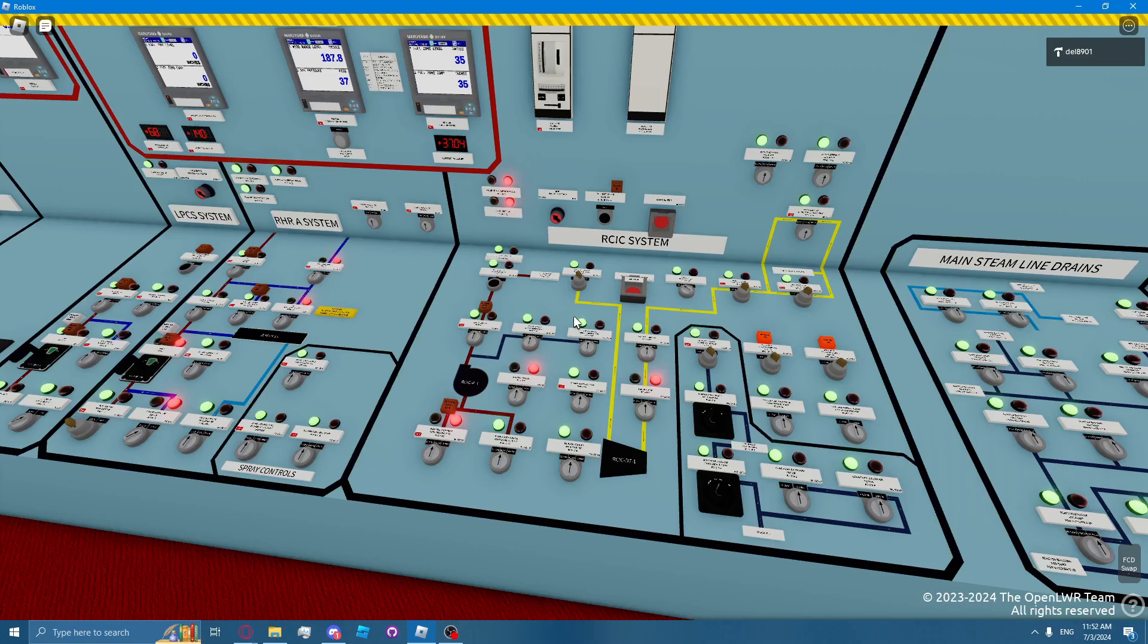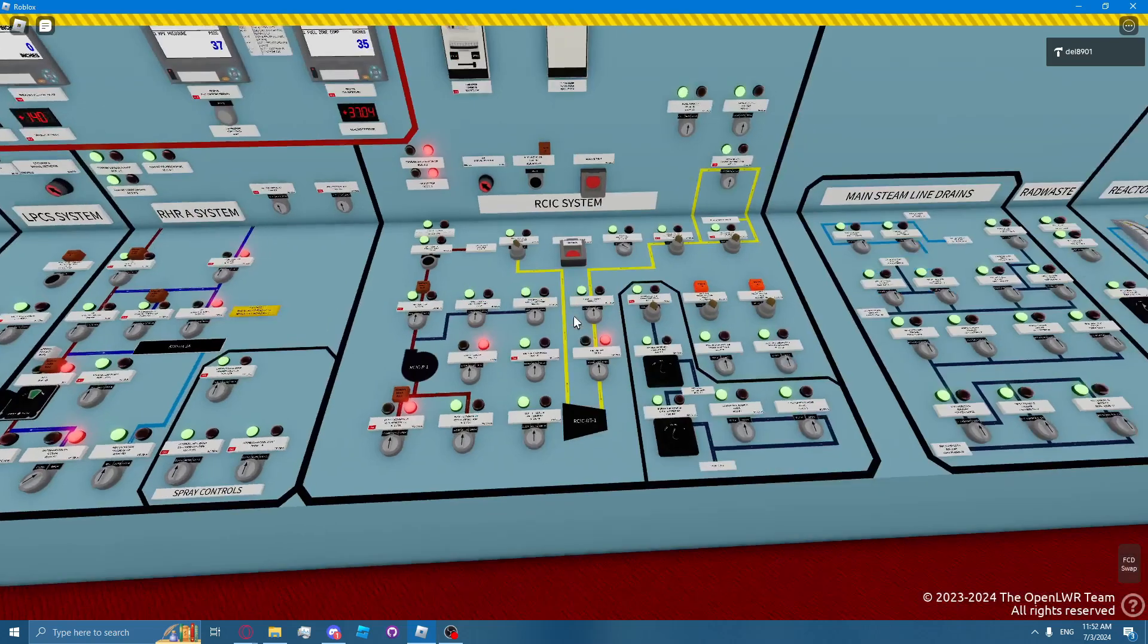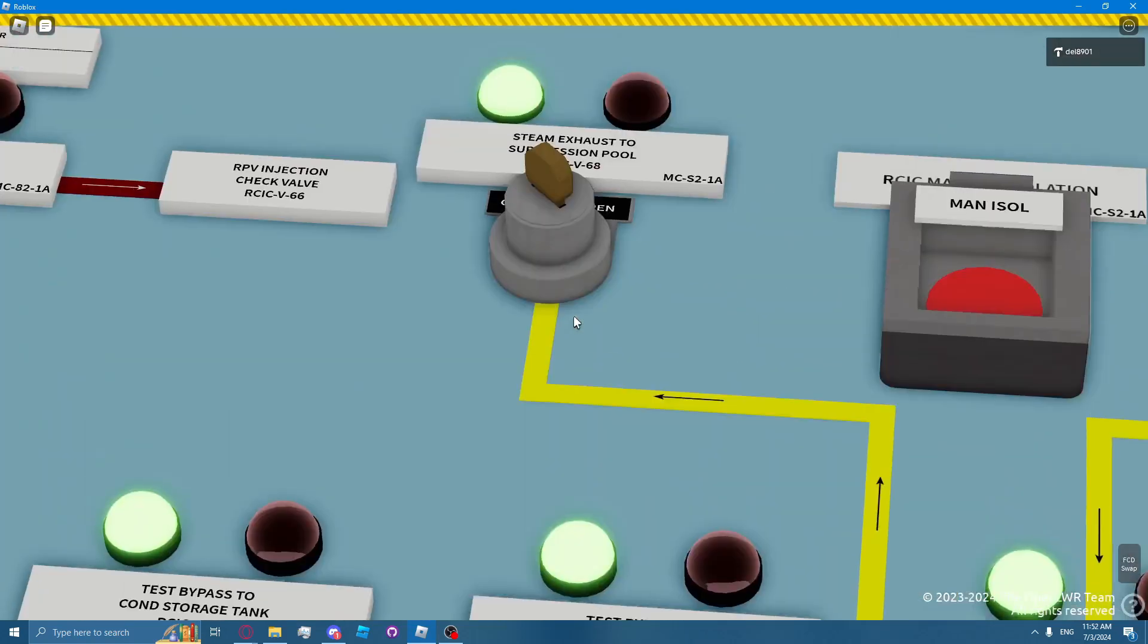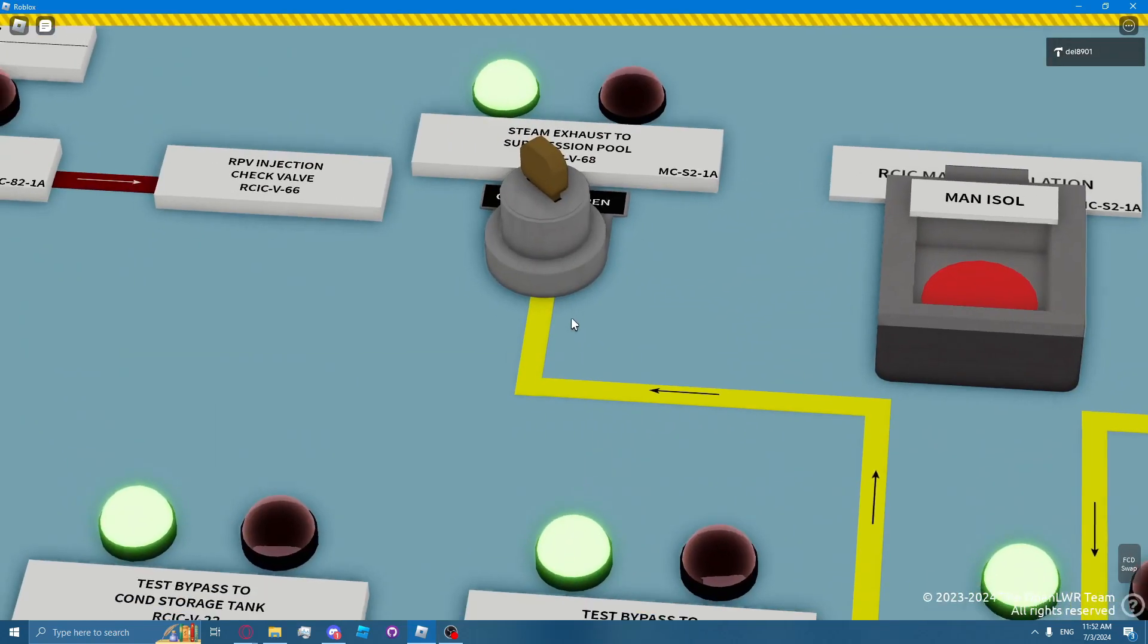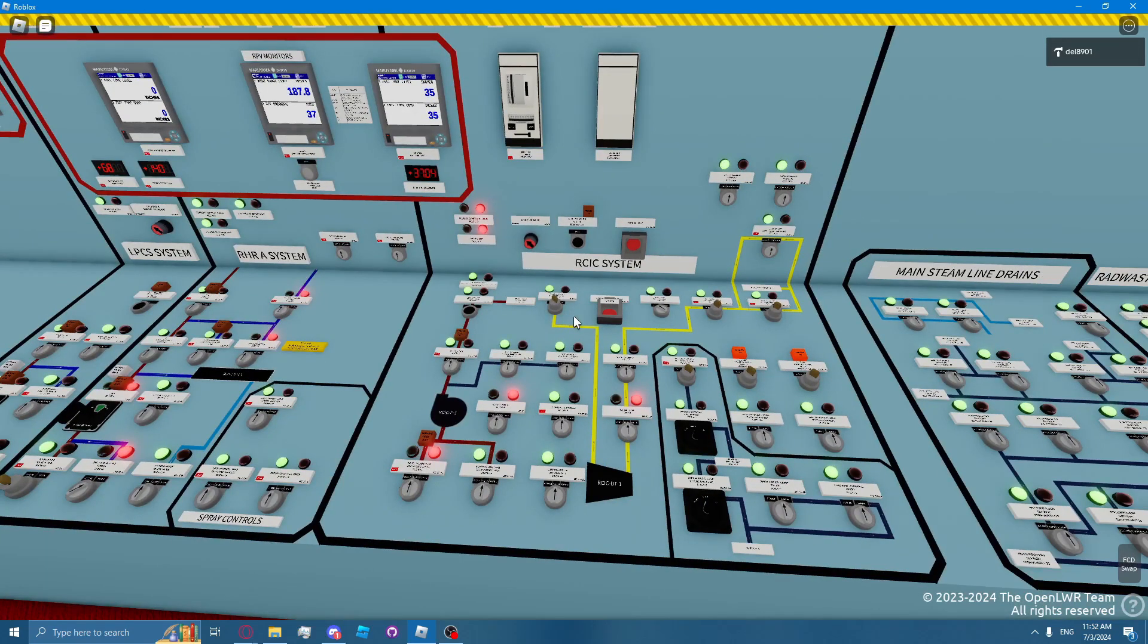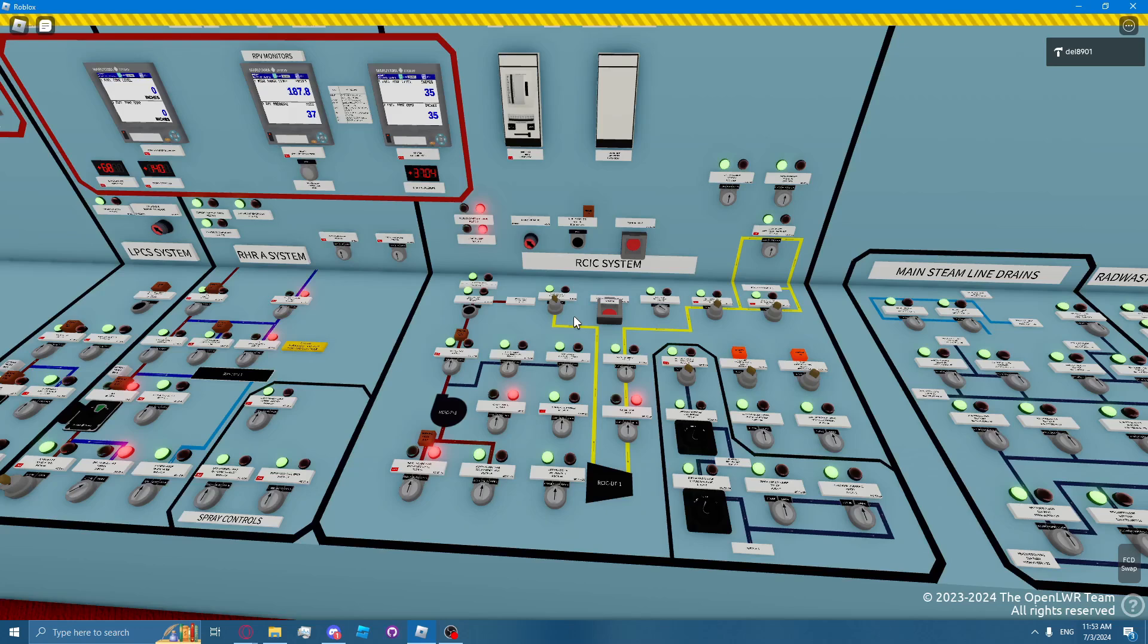The RCIC turbine exhaust line, here, takes steam from the RCIC turbine and discharges it to the suppression pool below the water level. The exhaust line is protected from overpressure by tripping the RCIC turbine on high exhaust pressure. There's additional overpressure protection from rupture discs, which relieve exhaust line pressure to the RCIC room.